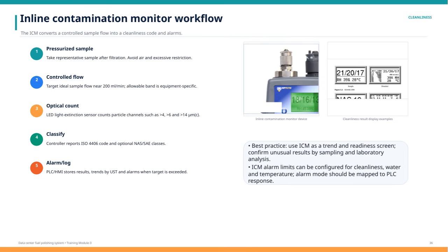Following particle detection, the system classifies the data and reports an ISO 4406 cleanliness code, with optional classifications like NAS or SAE. Finally, the results, trends, and alarms are logged and stored in the PLC or HMI. When cleanliness limits are exceeded, the system triggers alarms to prompt action. As a best practice, we use the ICM primarily to monitor trends and overall readiness. Any unusual readings should be verified through traditional sampling and lab analysis.